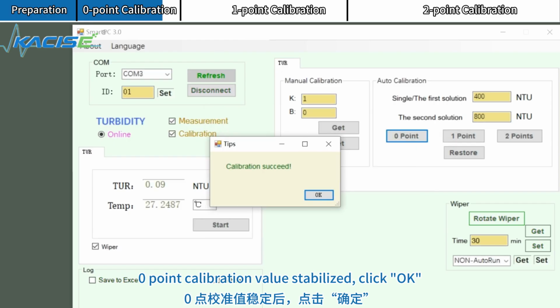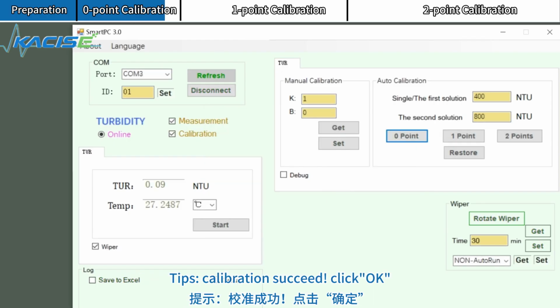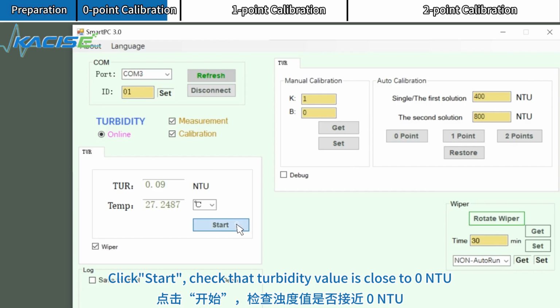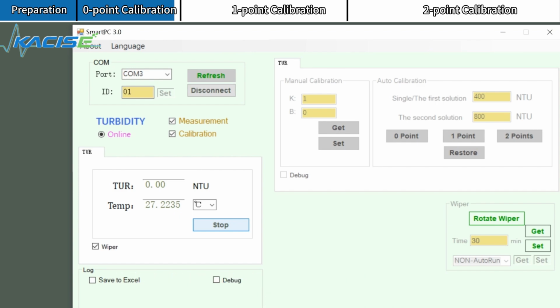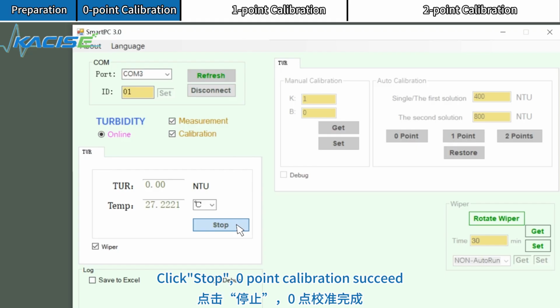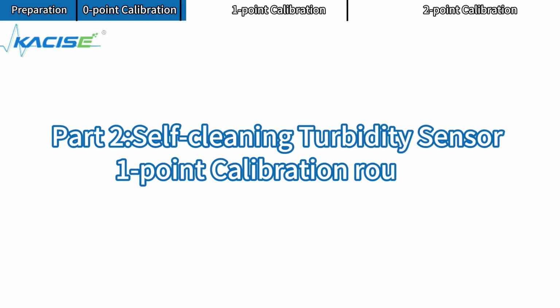Click OK. Tips: calibration succeed. Click OK. Click Start. Check that turbidity value is close to 0 NTU. Click Stop. 0 point calibration succeed. Part 2. Self-cleaning turbidity sensor.